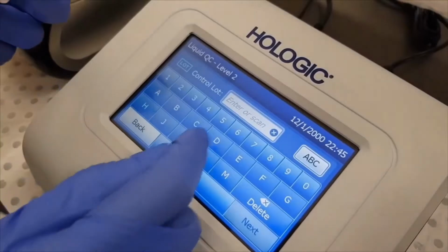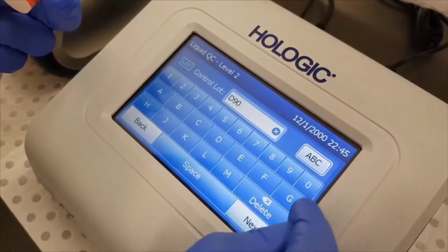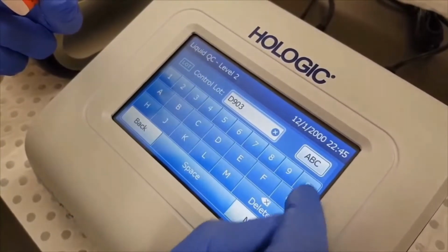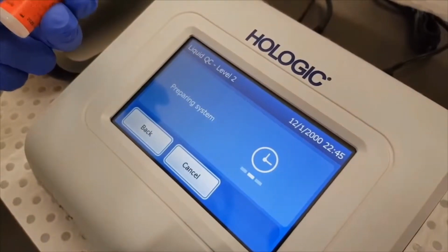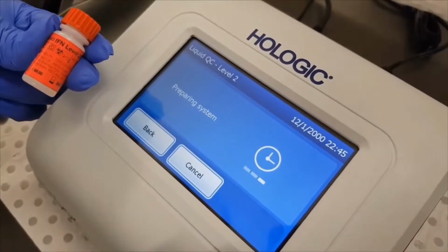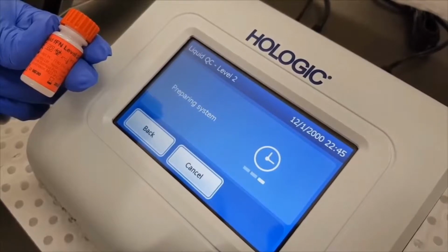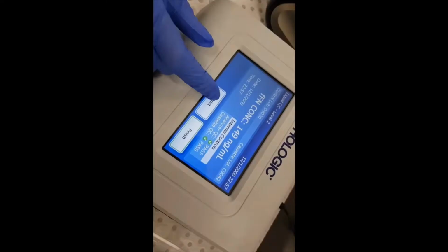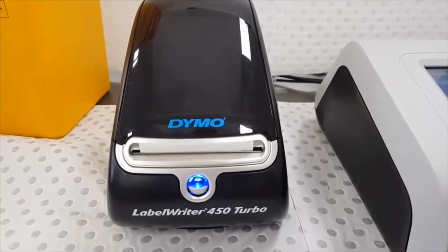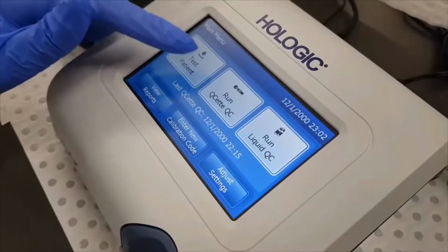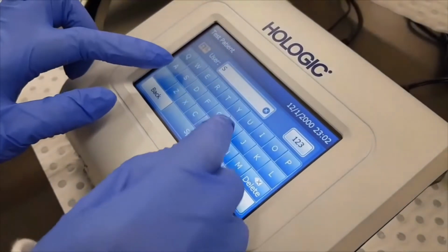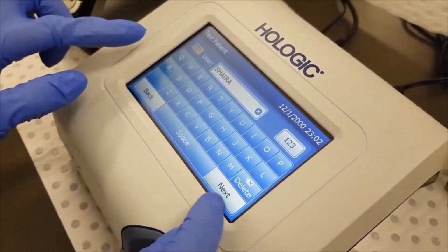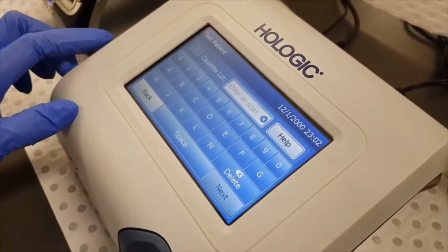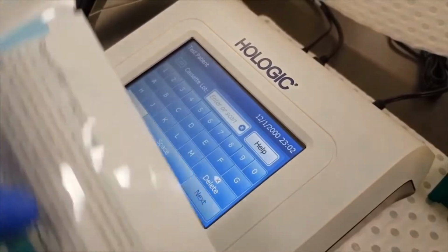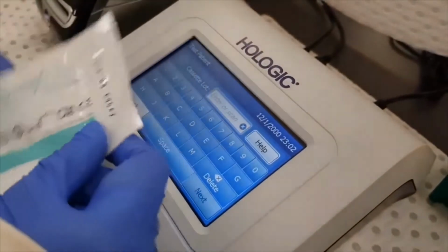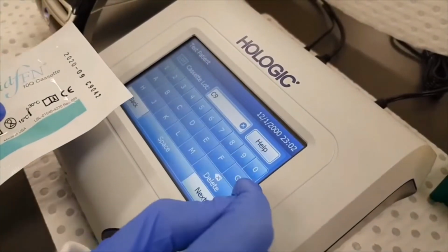Repeat the same steps with level 2 as what was completed with level 1. Prepare the system and once set up, wait for the analysis and print the results before finishing the quality control procedure. Begin patient testing by selecting Test Patient on the main menu. After entering your user ID, copy the cassette lot number into the system and press Next to enter the patient sample ID.